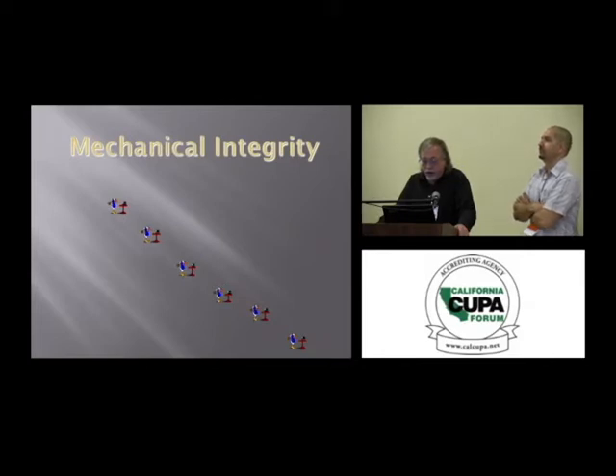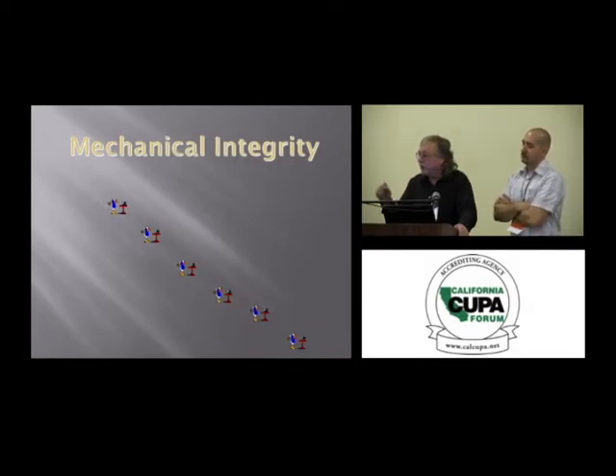One of the biggest things we're finding in recent years at doing inspections, is coming to their pressure relief valves, their safety relief valves, and the supporting piping. In the old days when we first put these systems together, we only had a few different relief valves to pick from. I'm talking about rate of relief, pounds per minute for the safeties. And those were much bigger on most vessels than what we needed. And we're finding that we can go to a much smaller relief valve, less pounds per minute released, and that allows us then to not relieve as much should we have an emergency, enough to keep the system safe, even in a situation for a fire so we don't have a BLEVE.